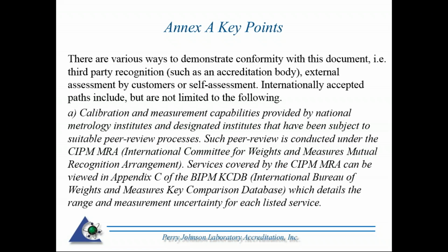So Annex A, again, in 17025, lists various ways to demonstrate conformity with this document: third-party recognition, such as an accreditation body, external assessments where the customer can go on site, or self-assessment. Internationally accepted paths include, but are not limited to, what is stated under A, which is what we just went over with National Metrology Institutes, and NIST in the case of the United States. So that's calibration and measurement capabilities provided by a National Metrology Institute and designated institutes that have been subjected to suitable peer review processes.